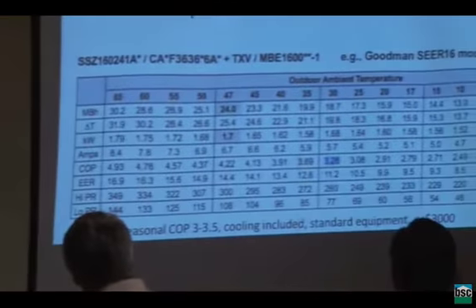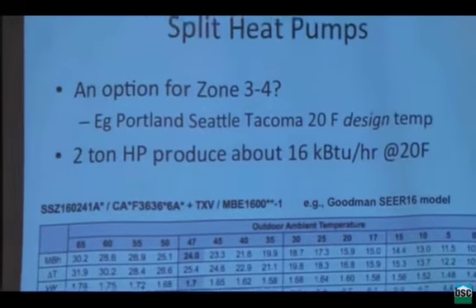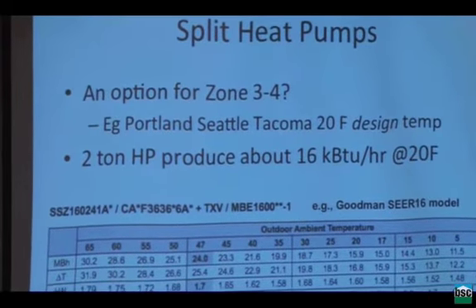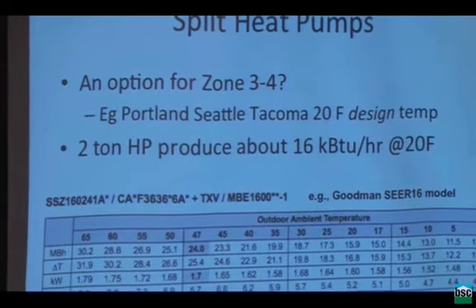And so actually, you can buy a 2-ton heat pump and it'll deliver 24,000 BTUs an hour, which is about right for a low load house. And when it gets really cold and your demand grows to 20,000, you maybe want to supplement with electric, but maybe not. But you can easily buy an off-the-shelf, low-cost system. So here I'm showing a 2-ton heat pump produces 16,000 BTUs an hour at 20 degrees Fahrenheit. So at 20 degrees Fahrenheit, I've already left Seattle. I'm going towards colder than Portland design temperature. And I can easily heat a low-load house with a 2-ton heat pump. Why 2 tons? Because that's the lowest cost-efficient heat pump I can buy as a commodity.